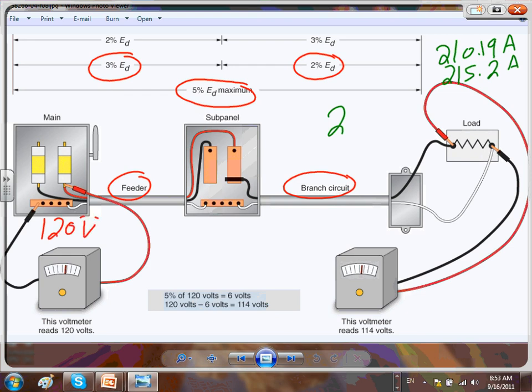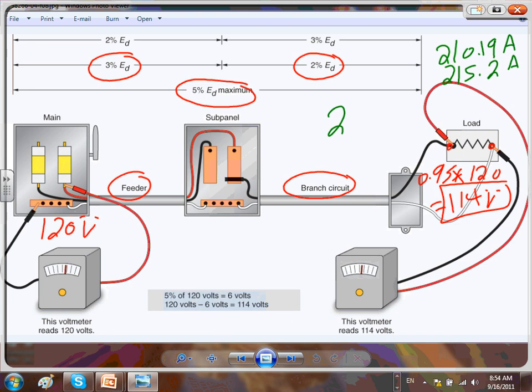For example: I have 120 volts at the panel. If I cut 5% out of 120, by the time I reach the equipment I have 95% of 120, which is 114 volts. I lost 6 volts. You started with 120 at the panel and ended with 114 — your equipment functions correctly at 114. You drop 6 volts because of resistance. We will do voltage drop calculations for AC and DC. The concept is that the voltage drops due to resistance in the conductor.